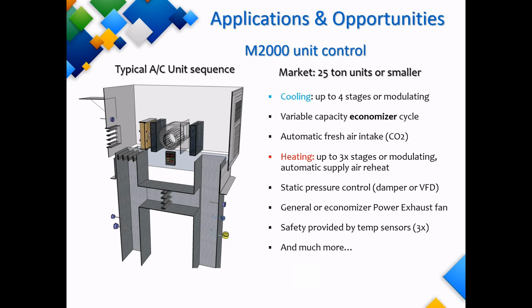There is a dedicated input for a static pressure transducer, so we can control either a bypass damper or a variable frequency drive in the case of a zoning system. The M2000 can control an exhaust fan based on occupancy or a power exhaust if the unit has one. Prolon's system always monitors the supply, return, and outside air temperatures, and we can apply low and high limits to cut out the heating or cooling if those temperatures get too high or too low.